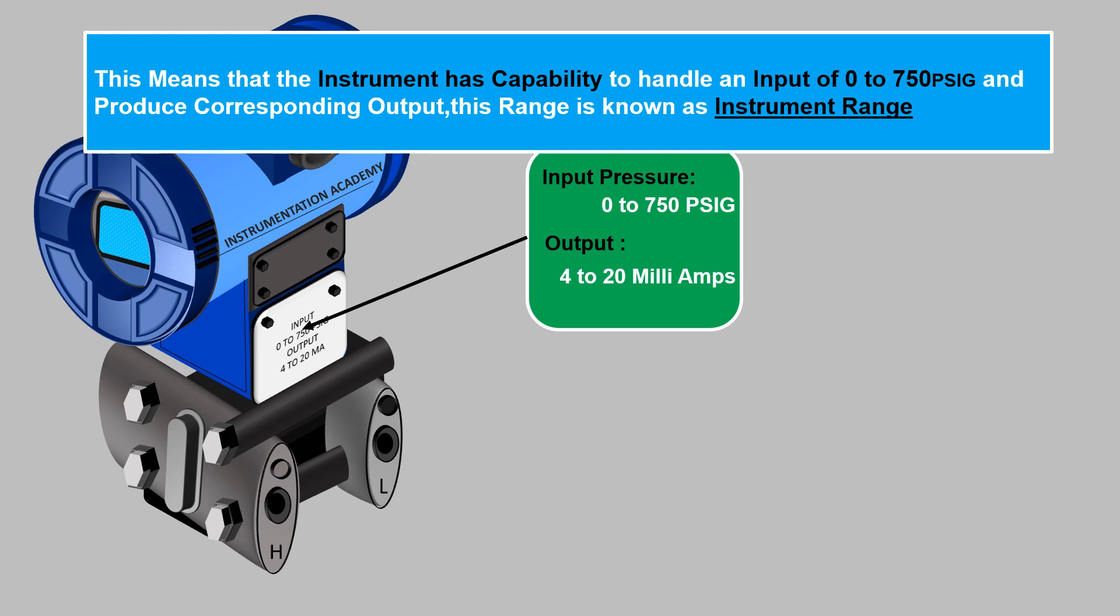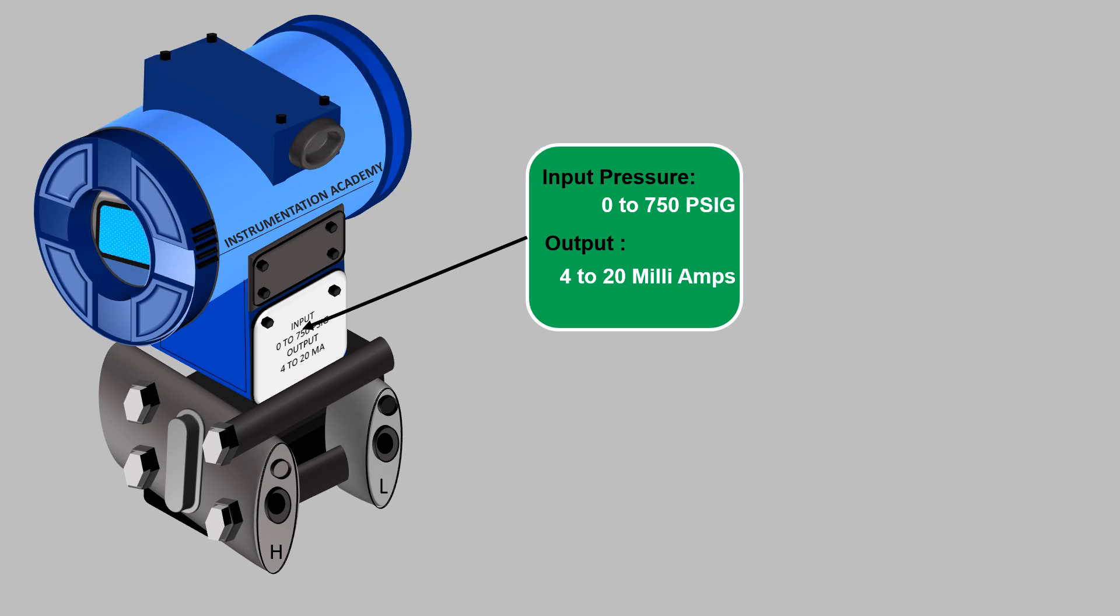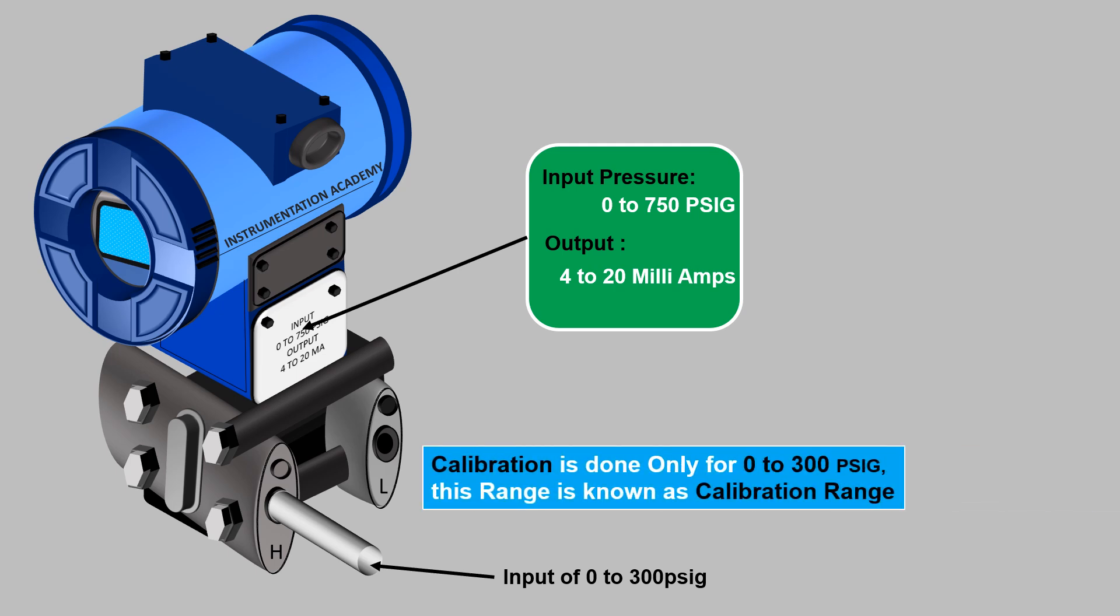Now consider that we need to use this transmitter for an application where we need to give an input of 0 to 300 psig and get an output of 4 to 20 milliamps. Here calibration is done only for 0 to 300 psig. This range is known as calibration range.